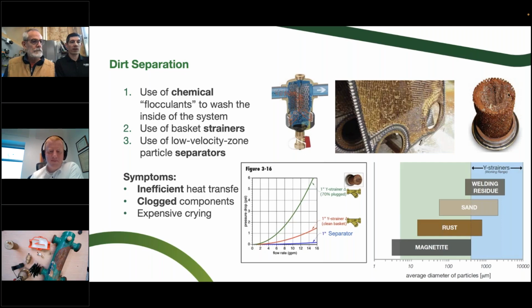You can use a Y strainer. The problem is whatever you catch stays in the fluid path forever. So if you caught that welding glove, you now have to live with a welding glove obstructing your flow for the rest of time, unless you're able to get that out of there. We got the one returned back, and we had to pull the glove out after it had been shipped back to Caleffi North America in Wisconsin. So what I prefer is that we have that dirt hit something and fall down out of the fluid path, and that's what a dirt separator does. It's like it's grabbing the debris and throwing it into a bucket.